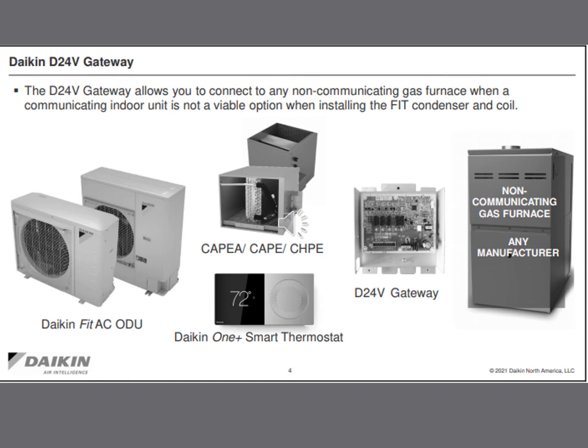Now with the D24V Gateway, we can install the Daikin FIT outdoor unit, we can install the communicating EEV coil and the Daikin 1 thermostat, and then match that up to any non-communicating gas furnace from virtually any manufacturer. This allows us to take the Daikin FIT systems into applications where previously we weren't able to do so.